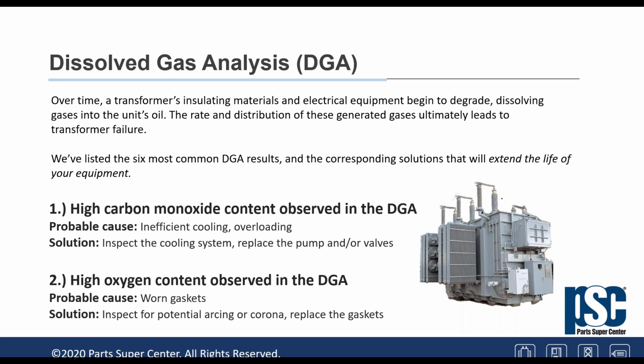But again, high carbon monoxide content is the first thing we call out. It's inefficient cooling, overloading. All this stuff is a consequence of the overheating of the unit. Now, why is there overheating? It could be various things: overloading, less efficient circulating equipment. But anyway, let's take one step at a time. Again, as we see here, high carbon monoxide is usually inefficient cooling and overloading. But there's another thing that could be happening. Carbon monoxide could also be a consequence of some overheating of the core of the unit, which could again be a consequence of abusing the unit.